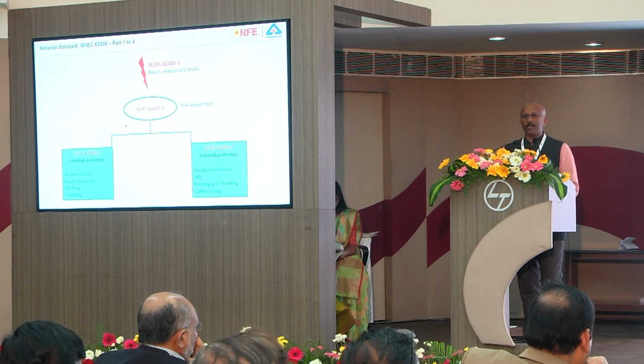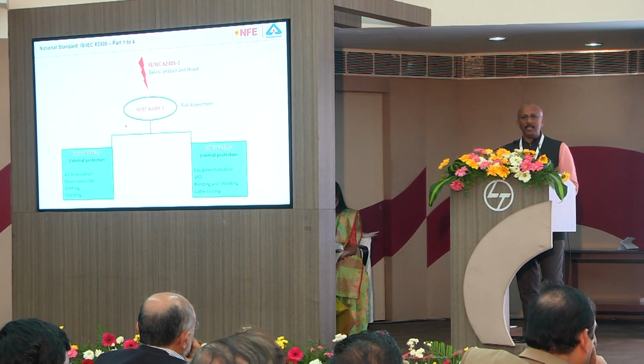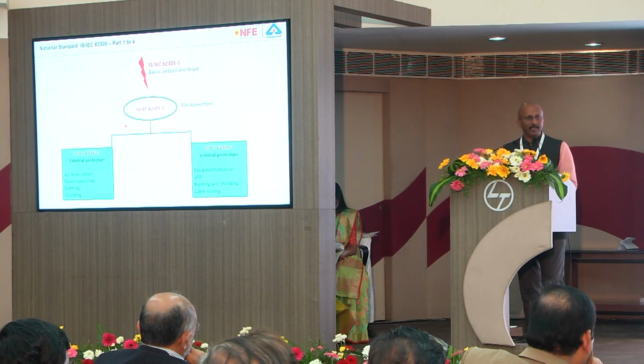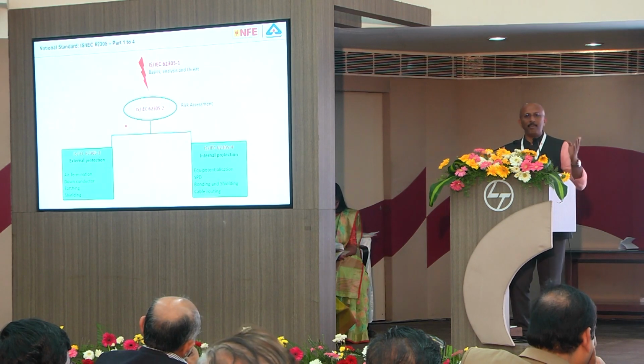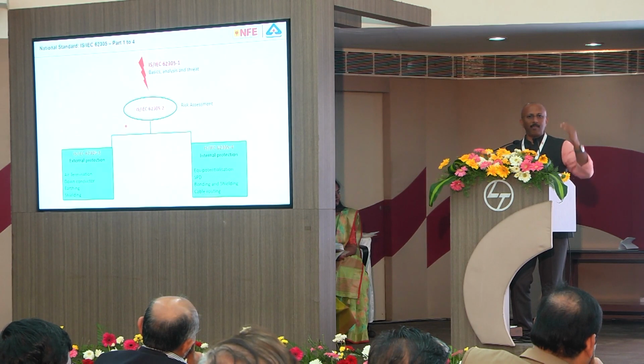When it comes to a project, a lot of times I have seen people asking very seriously, I want a risk assessment report. Without a risk assessment report, the next step is not possible. Sometimes I get a feeling that the risk assessment is going to protect the building. The risk assessment is just a paper which tells you what level you need. For that you have a table in NBC: data center level 1, hospital level 2, something like that. There is a table, you can simply refer to that. So even if you are putting level 1 or level 2, it does not make much difference.